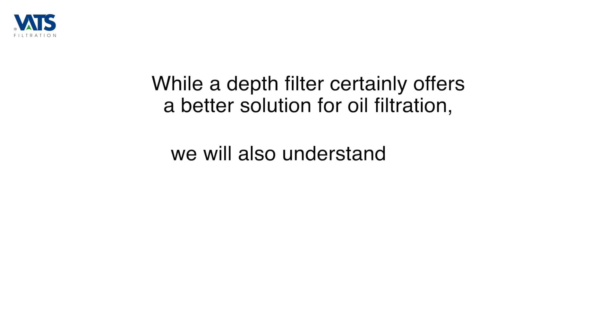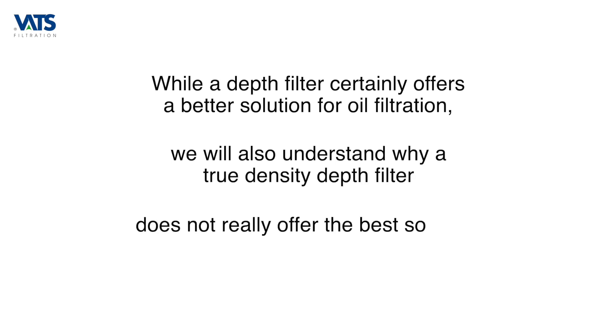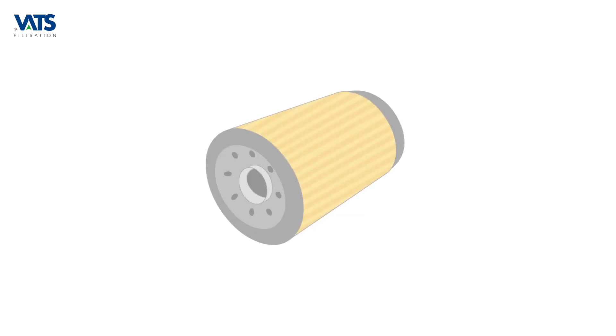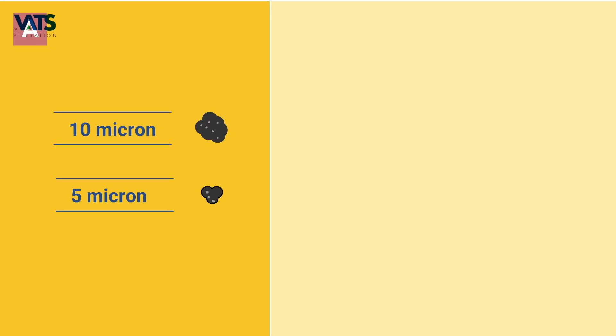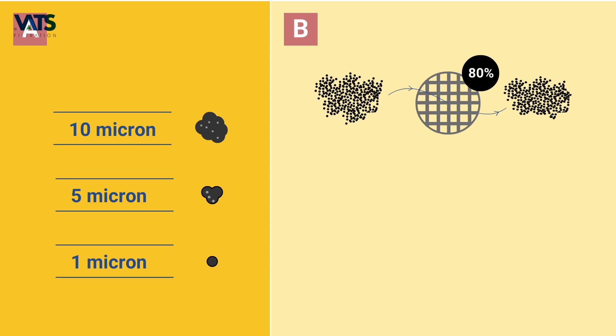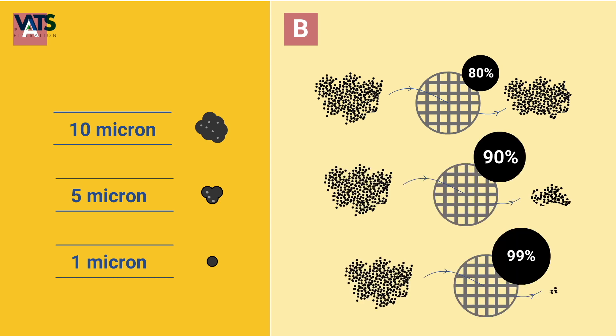While a depth filter certainly offers a better solution for oil filtration, we will also understand why a true density depth filter does not really offer the best solution. The choice of filter element is mainly based on two factors: A) the particulate size removal threshold, which is the largest size of particle that we can let pass through the filter, and B) its efficiency, which is decided by the particles it retains compared with the particles it lets pass.